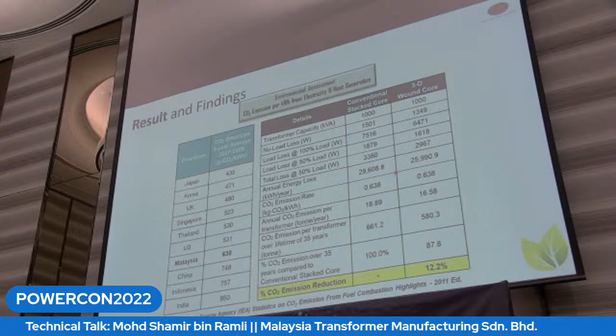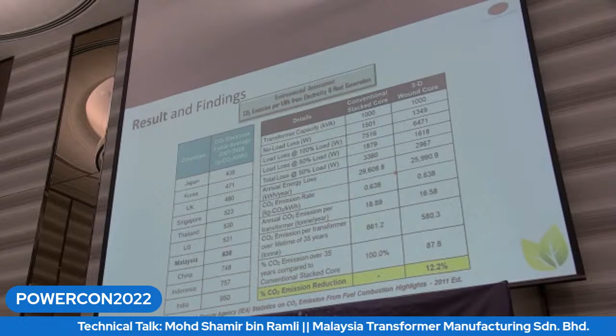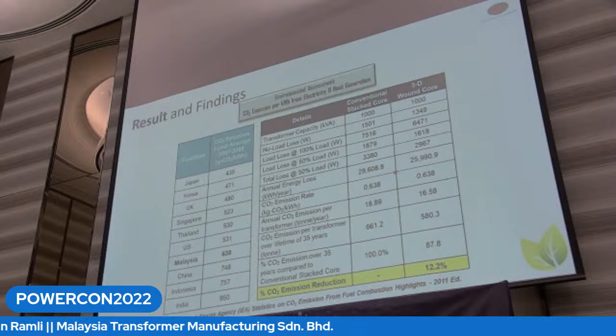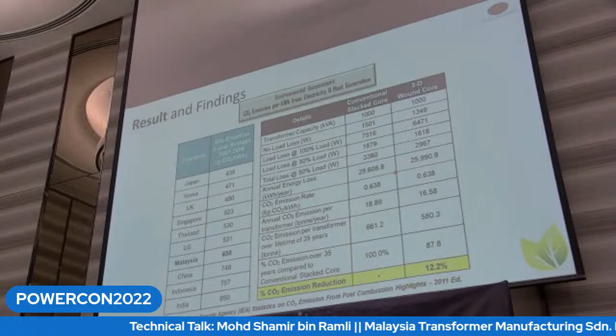In terms of the environment, we look at countries all over the world in terms of CO2 emission on a 3-year average, from Japan to India. For Malaysia at the time, it was 638 grams of CO2 per kilowatt hour. But if we look at the transformers, for a conventional stack core, when you compare the transformer capacity, load loss, annual energy loss, and CO2 emission rate, you can see that the 3D wound core has a better performance.